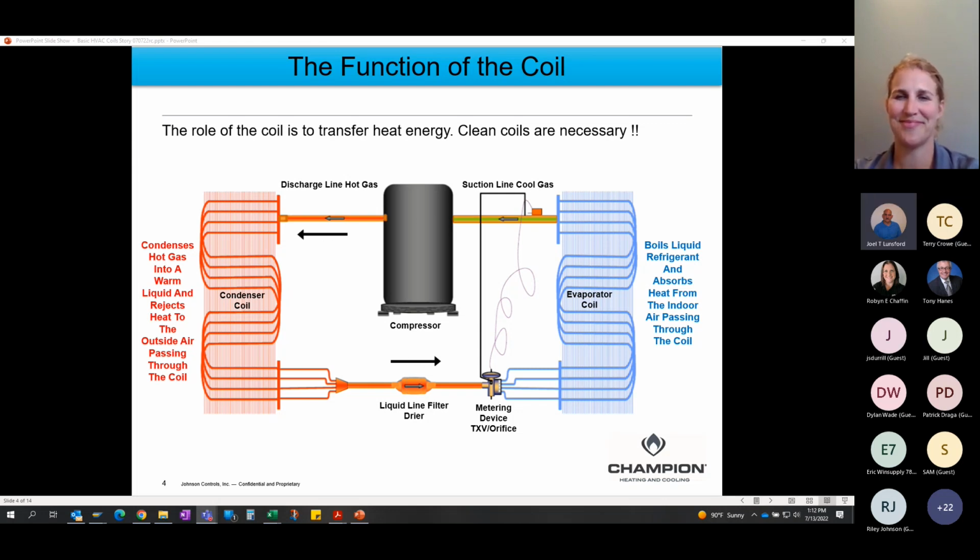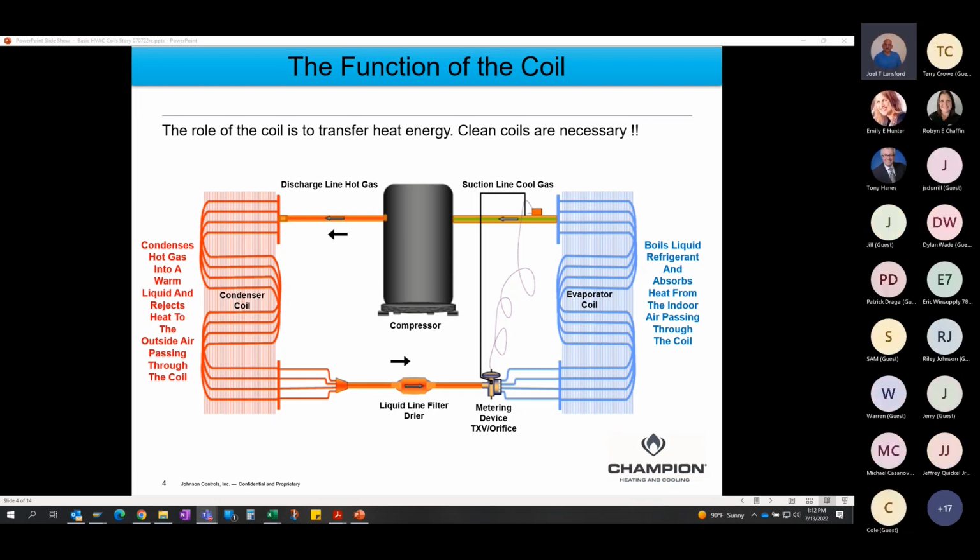That is correct. Based on the filter technology, to your good point, we may have to have larger return air ductwork, and we may have to have more return air registers. So absolutely, on the indoor coil especially, we want to maintain the proper airflow across that coil. The higher the MERV rating, or the more filtration on the air going through that coil, the more we want plenty of extra or larger return. Those are serious considerations when you're looking at utilizing aftermarket media filters. Good, excellent point. Thank you for that input.